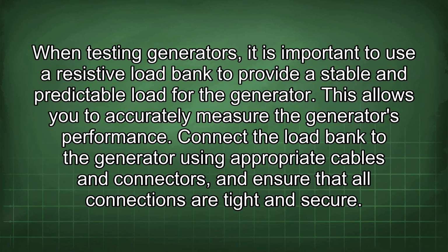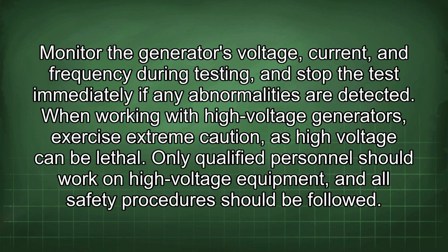When testing generators, it is important to use a resistive load bank to provide a stable and predictable load for the generator. This allows you to accurately measure the generator's performance. Connect the load bank to the generator using appropriate cables and connectors, and ensure that all connections are tight and secure. Monitor the generator's voltage, current, and frequency during testing, and stop the test immediately if any abnormalities are detected.